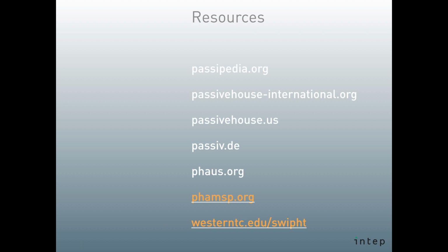Interestingly enough, the passive house, I think, is actually a model where a forced air system works much better. We sort of have it backwards. In conventional construction, where you have large heat loads and low temperatures surrounding you, a radiant heat system would make you much, much more comfortable. But in this particular model, where it's so well insulated, all you're really conditioning is the heat inside. That's where a forced air system shines, because it does that very quickly and efficiently. So it's funny in that the traditional way of building is exactly backwards. And we find these systems here are very cost effective.